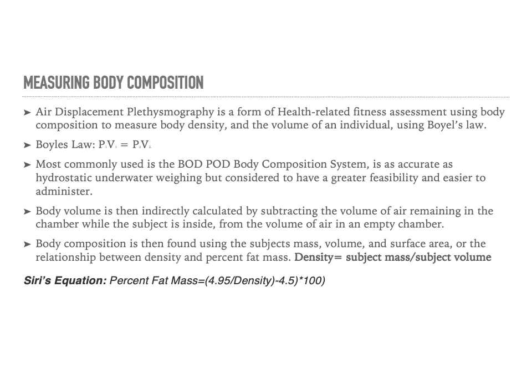The BODPOD is an accurate way to measure body composition, and it is more accurate than hydrostatic underwater weighing. It is considered to have greater feasibility than hydrostatic underwater weighing because it's easier to administer, takes less practice, and is way less expensive. By using the BODPOD body composition system, the body volume is indirectly calculated by subtracting the volume of air remaining in the chamber while the subject is inside from the volume of air in an empty chamber. Using this difference, body composition is found using the subject's mass, volume, and surface area.